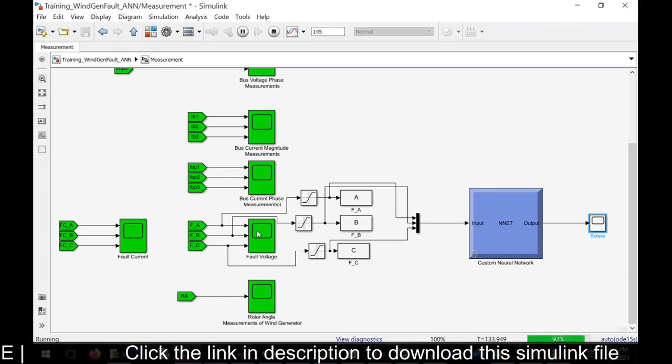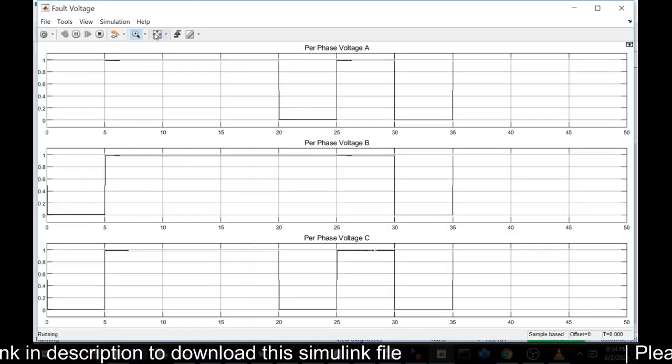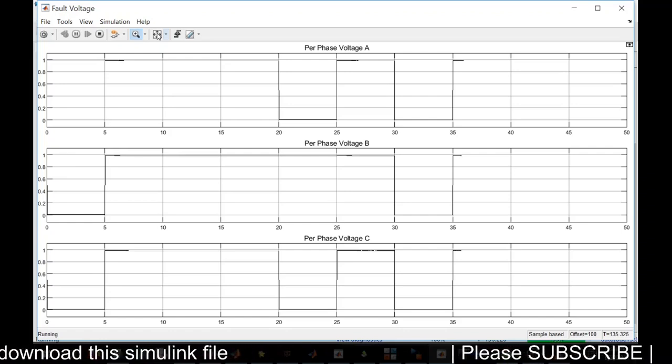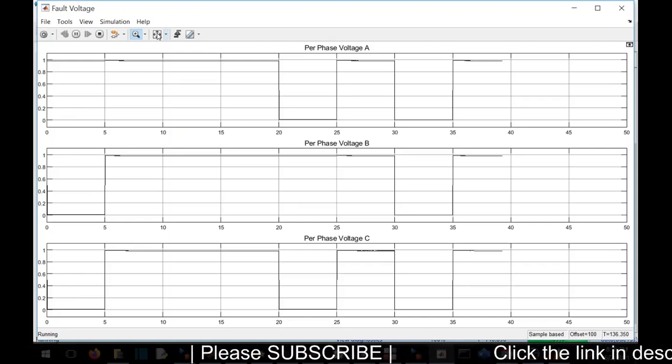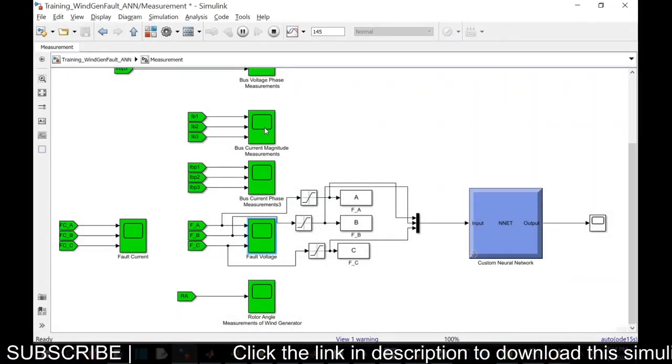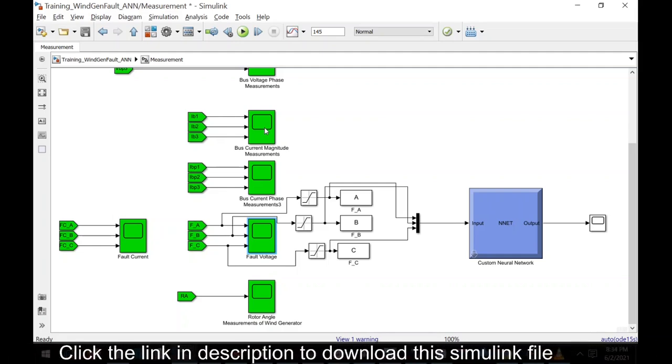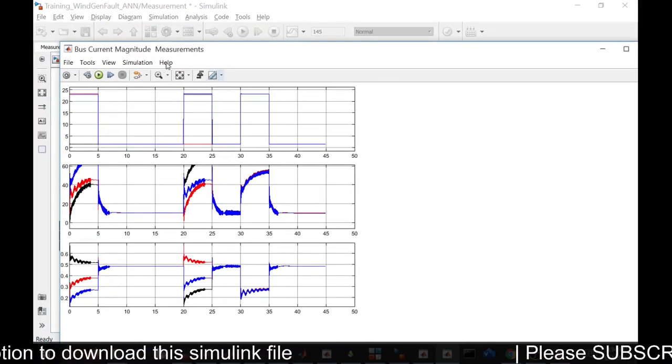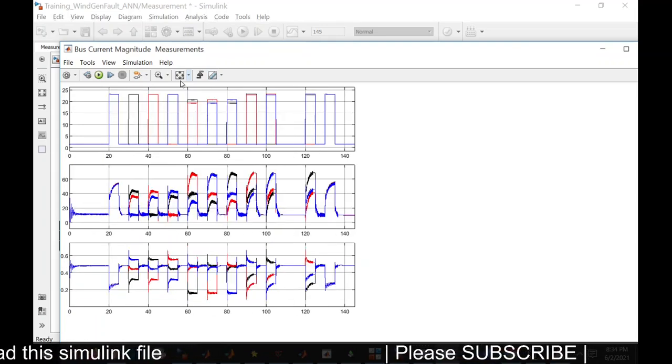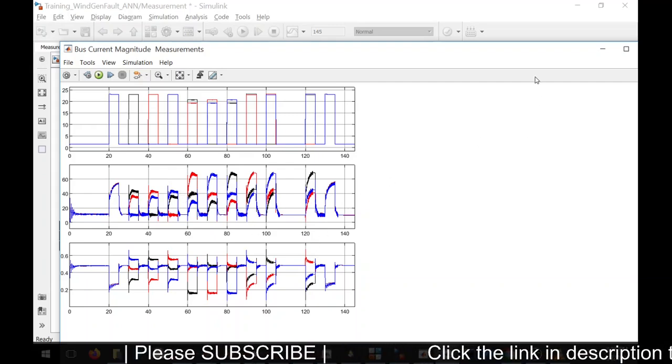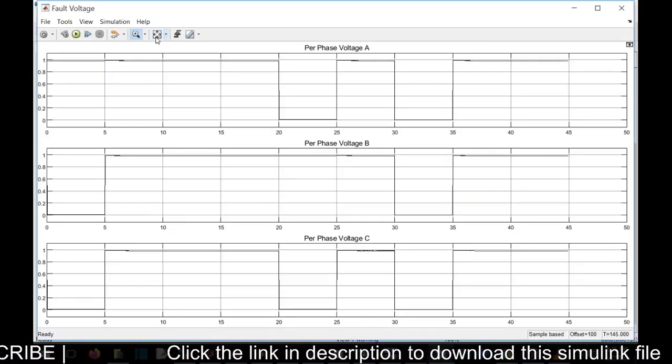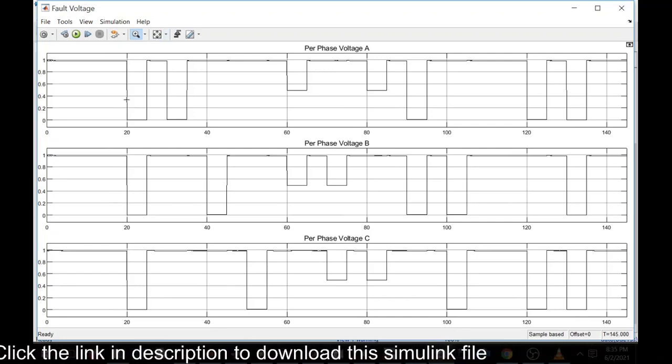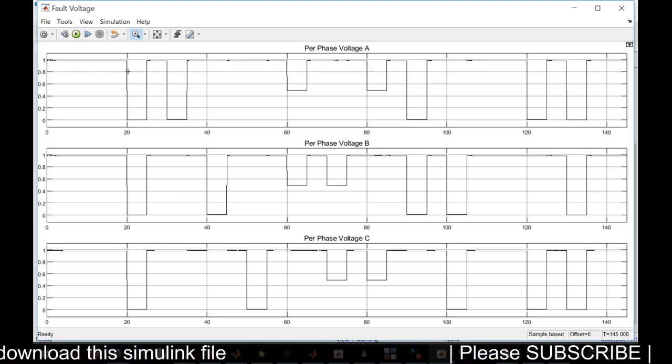See, we have various other scopes to measure the voltage. This is the scope which measures the voltage of all the three phases. Current, current magnitude. When the fault is being generated, you can see the waveform changing. All the values are given in terms of per unit, and only the magnitude is given.